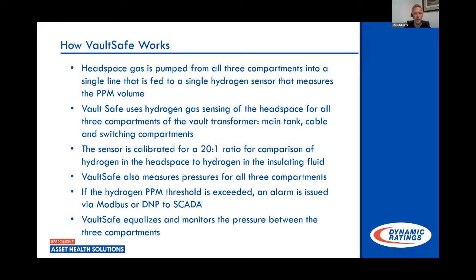These compartments, you can't have mixing of oil. So any type of oil monitoring was going to require that at least 3 sensors be purchased. When you start talking about 3 separate hydrogen sensors and 3 separate pressure sensors, you're starting to get into quite a bit of money you're having to spend to get monitoring on a transformer, to monitor the total system.